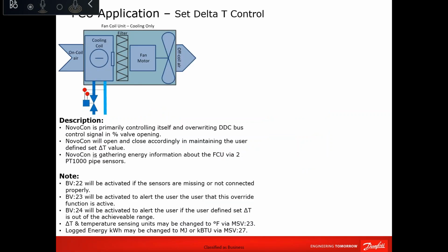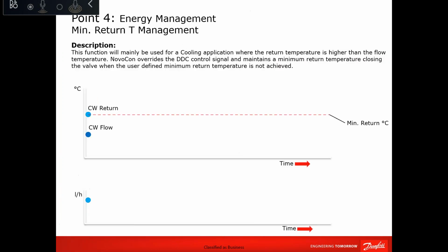So how does it work? It's primarily controlling itself and overriding the DDC BMS control signal. So when you set the minimum delta T, the Novocon is not controlling via the normal thermostat or via the BMS. It's controlling only based on the minimum delta T. So based on the application, it's flexible. You can choose any of these types of control sequence.